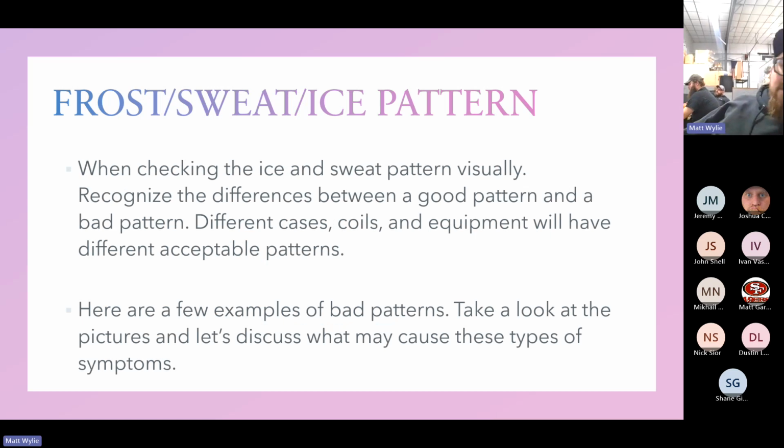Frost, sweat, and ice pattern. When checking the ice and sweat pattern visually, recognize the difference between a good and bad pattern. Different cases, coils, and equipment have different acceptable patterns.